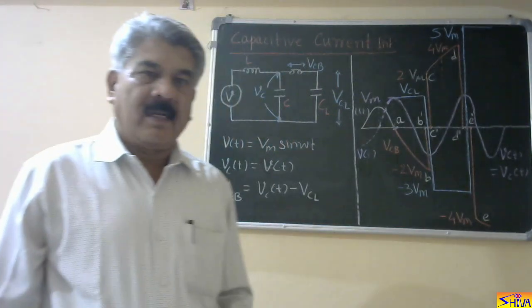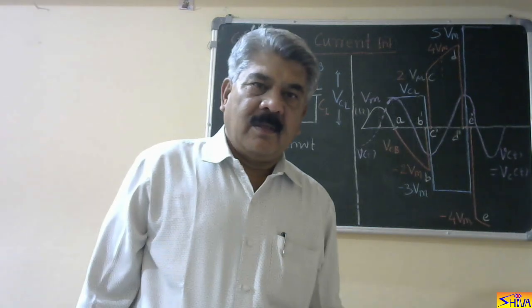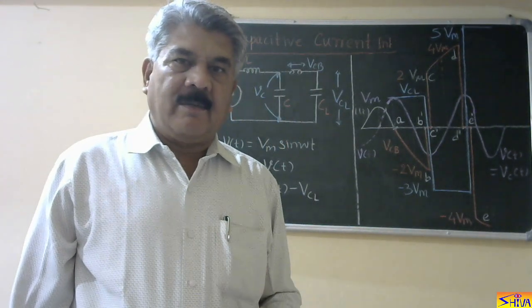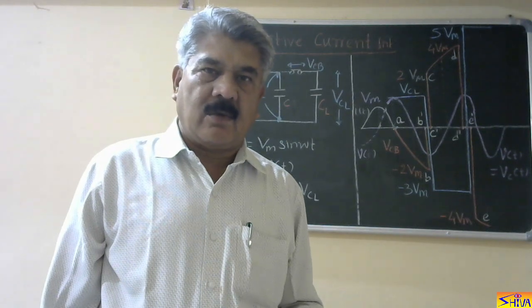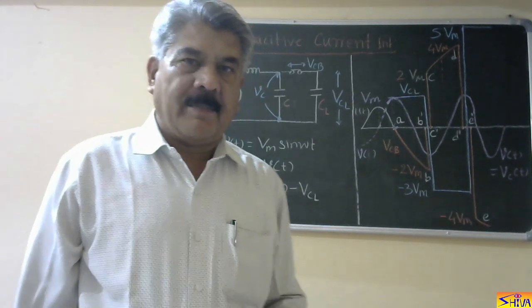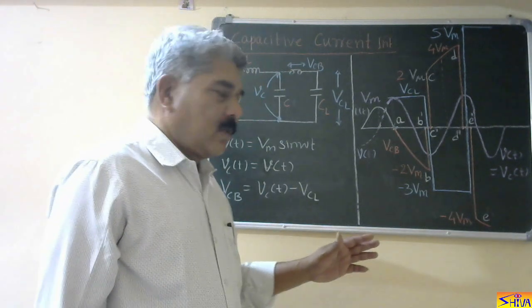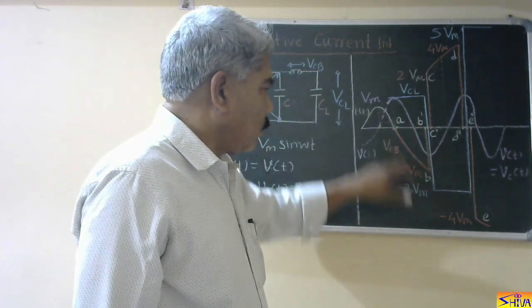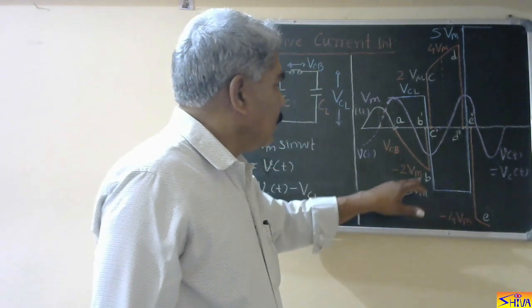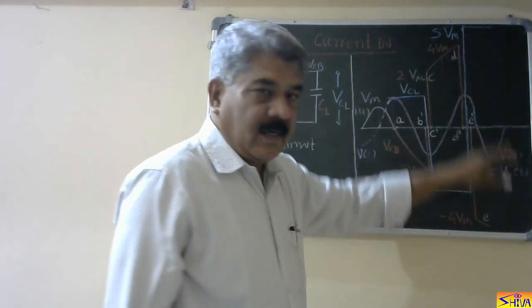Therefore, it is said that when circuit breaker is interrupting low capacitive current, that of long transmission line at no load or shunt capacitor, the voltage across its pole changes from plus Vm to minus 3 Vm to plus 5 Vm and so on.